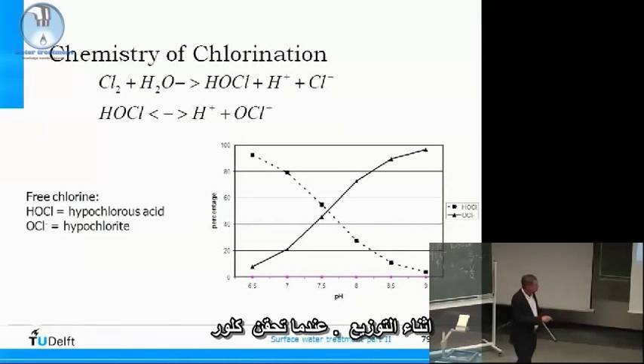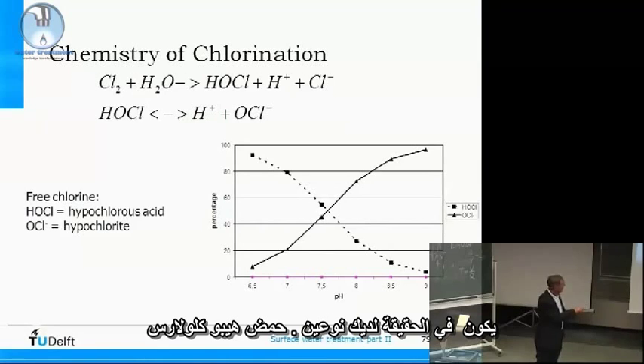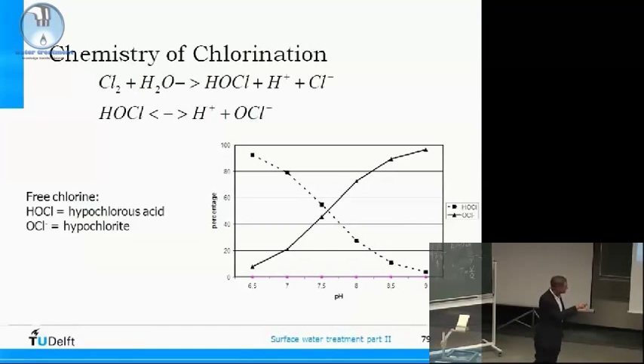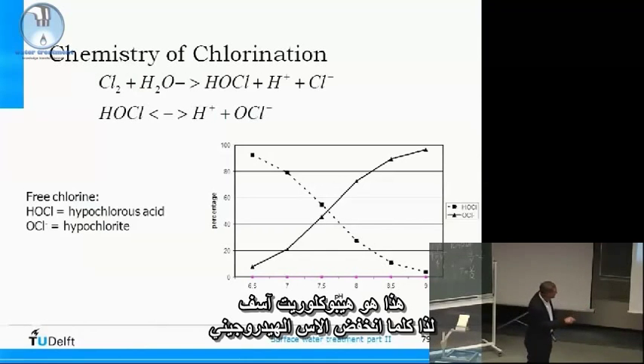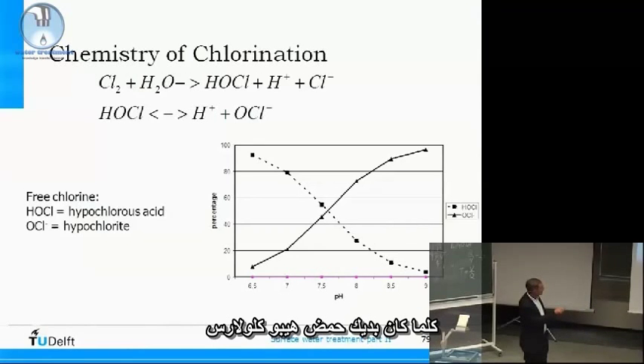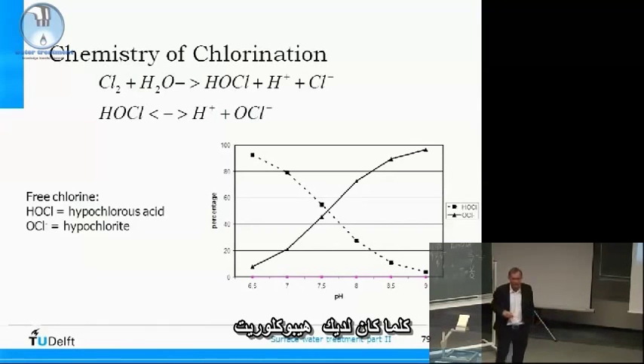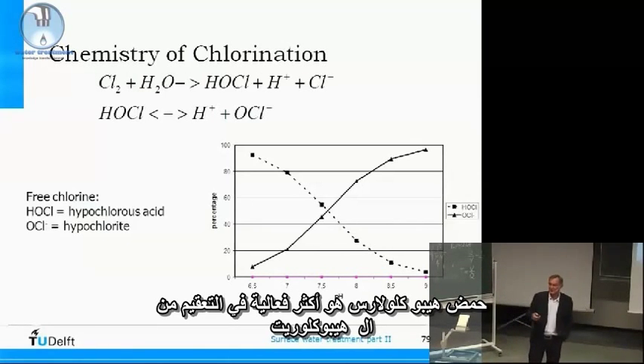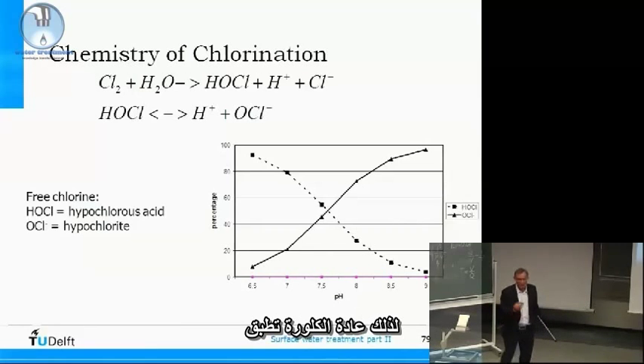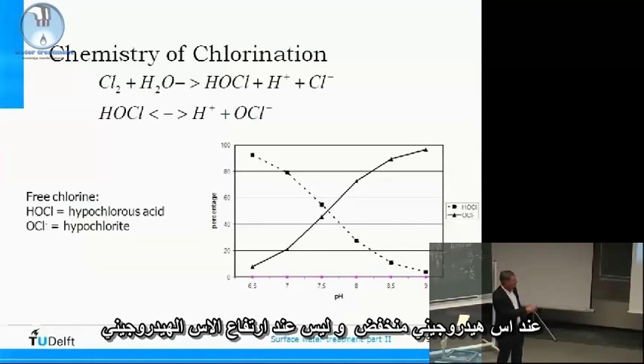When you dose chlorine, you have two species: hypochlorous acid and hypochlorite. The lower the pH, the more hypochlorous acid you have; the higher the pH, the more hypochlorite you have. Hypochlorous acid is more effective for disinfection than hypochlorite, so normally chlorination is applied at lower pH, not at high pH.